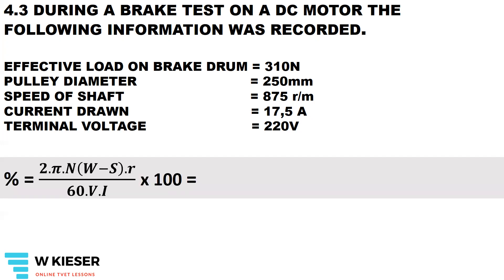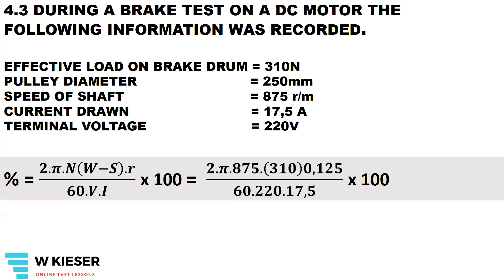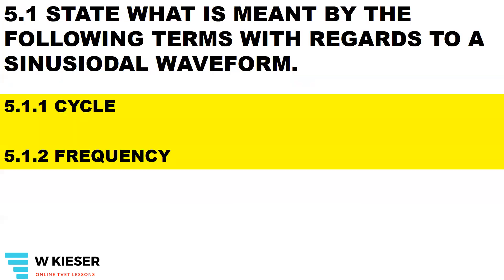For the direct method efficiency test, the formula is 2 times pi times the speed, multiplied by the effective force, multiplied by the radius, divided by 60, the supply voltage, and the supply current. When we substitute all those values into the equation, we end up with an efficiency of 92.2%.